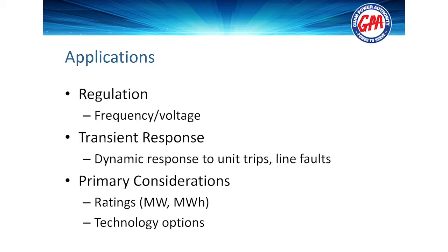So what are the applications for energy storage? One of them is regulation, and this is the one that I think is probably the easiest to grasp. What regulation means is that as you put on variable renewable generation, particularly solar, solar is a great product. It can have a lot of benefits to the system, but it also is probably one of the most dynamic power sources on the power system. So what does that mean to the utility? What that means to the utility is that they have to react to changes in their system load that they've never had to react to before.